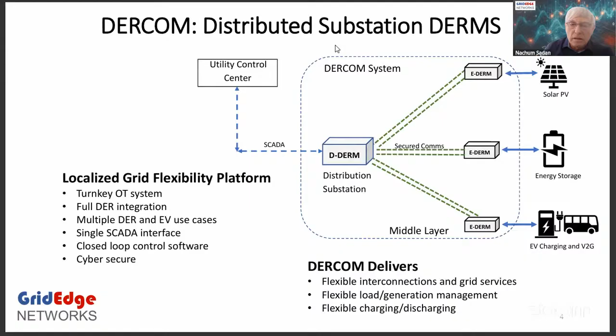It can run with or without centralized DERMS. The brain of the system are the closed-loop control algorithms that run on the DDERM in the substation and continuously monitor and control all DER assets that are attached to it. DERCOM also acts as a middle layer between the utility and the customer DER, providing a buffer and enhanced cybersecurity protection. DERCOM uses IEEE 1547 communication standards for interoperability and ease of integration.